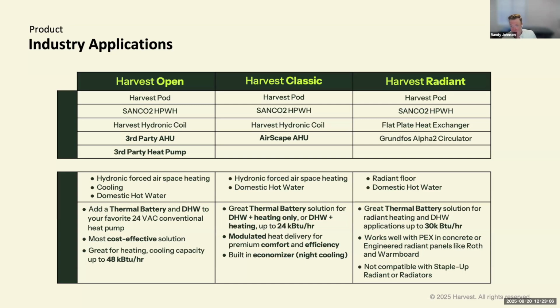Lastly, we have a radiant application as well, fairly common in the Rocky Mountain market. It lets us add a thermal battery to traditional hydronic solutions. This is 150 degree water temperature from our heat pump, so we're looking at about 140 to 145 delivery after going through a flat plate heat exchanger. The transfer material is quite important - we work very well with in-slab radiant and engineered solutions like warm board. It's important to understand the comfort and transferability in the home.